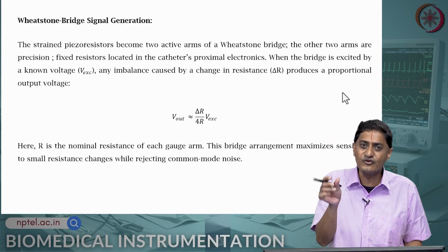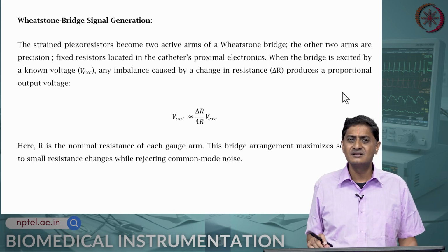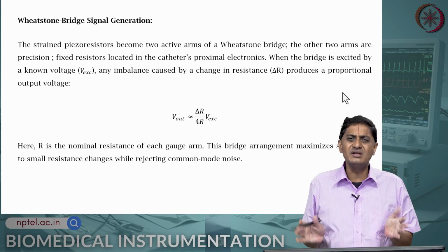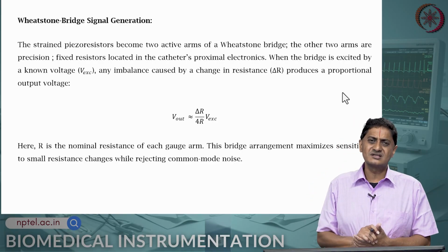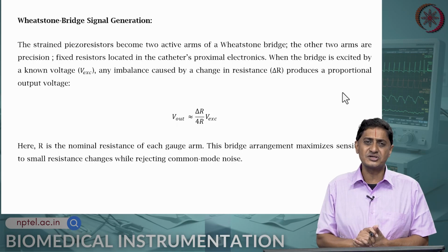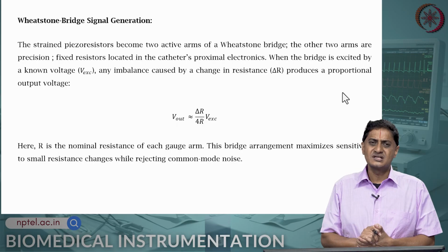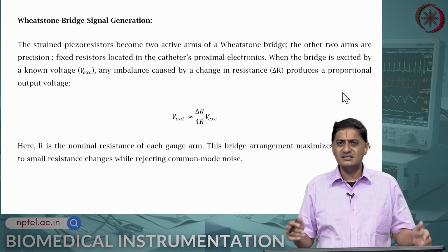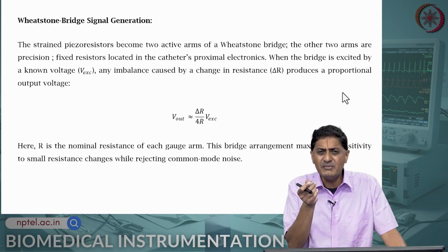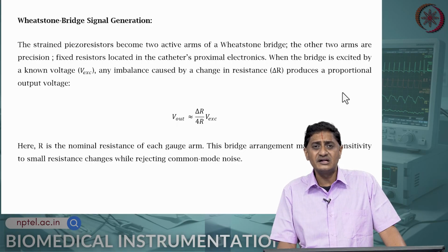When the pressure or force changes by a teeny tiny bit. There is also very minimal common mode noise. So, it is a highly accurate and high fidelity pressure sensing system, because the very minimal changes in resistance are very quickly and accurately captured with very high fidelity.